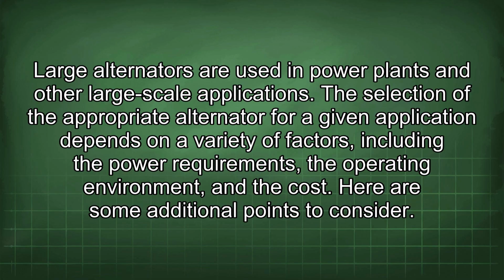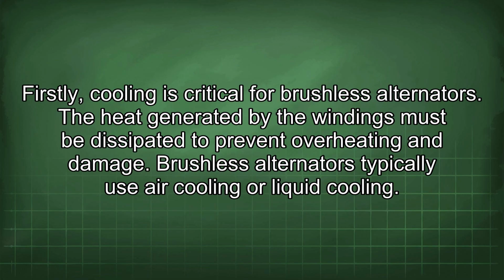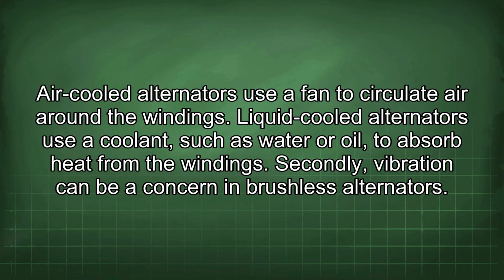Here are some additional points to consider. Firstly, cooling is critical for brushless alternators. The heat generated by the windings must be dissipated to prevent overheating and damage. Brushless alternators typically use air cooling or liquid cooling. Air-cooled alternators use a fan to circulate air around the windings. Liquid-cooled alternators use a coolant, such as water or oil, to absorb heat from the windings.